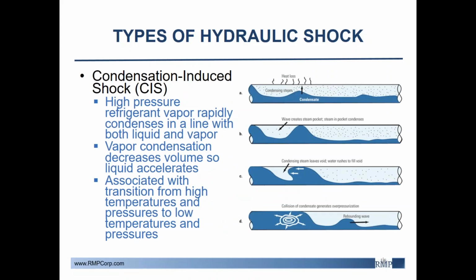condensation-induced shock. High-pressure refrigerant vapor rapidly condenses in a line with both liquid and vapor, and as the vapor condenses, it undergoes a significant decrease in volume. This causes the liquid to accelerate and ultimately overpressurize the system. This type of hydraulic shock is most common, especially in low-temperature ammonia systems, and is associated with the transition from high temperatures and pressures to low temperatures and pressures.